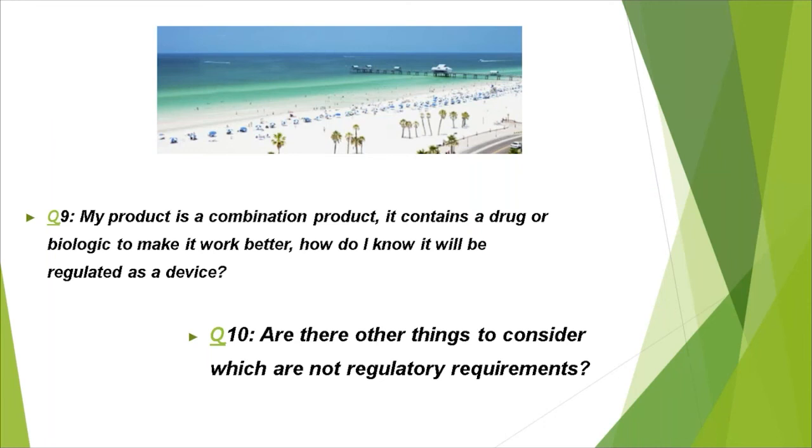If it's a combination product, if the product includes a biologic, then the pathway is a biologic pathway. If the product includes a drug with it, then the primary mode of action determines the regulatory pathway. And the primary mode of action, we always try to make that be a device because it's a much easier, less burdensome pathway. And with the device pathway, we submit any application documents to the device people at FDA, and typically they're already biased to keep it a device if possible.